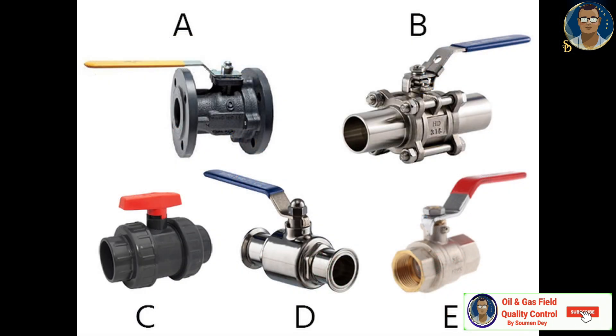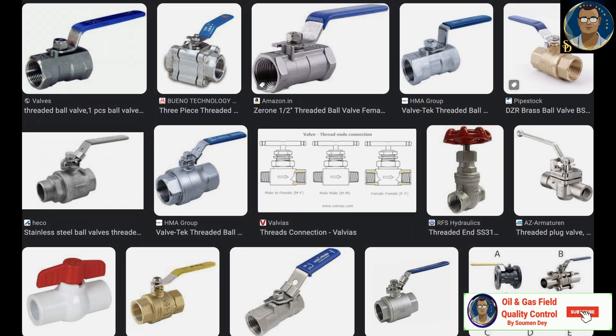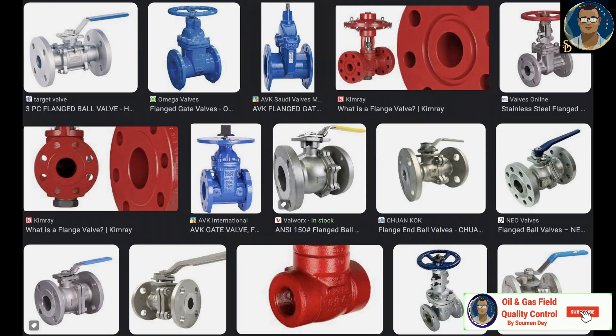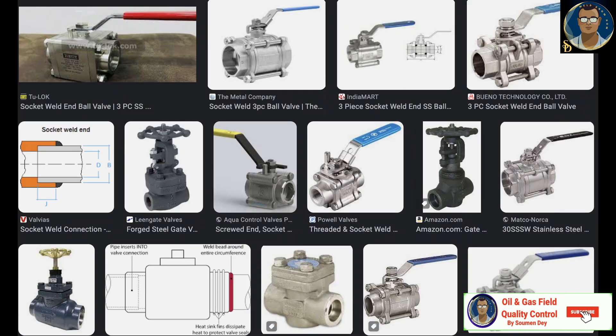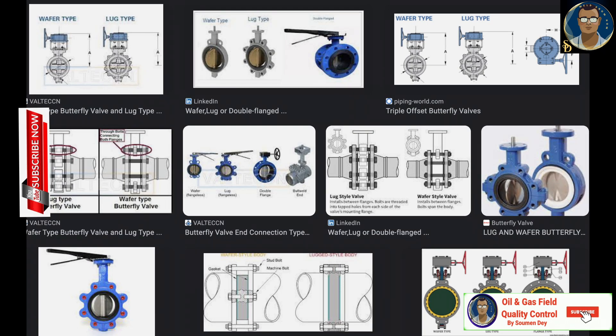Types of valve based on their end connection. The connection type must be compatible with the piping. Types include: screwed or threaded, mostly used for instrument or sample point connections; flanged, one of the most commonly used ends for piping; butt welded, widely used in high pressure and high temperature operations; socket welded, used in small bore piping where threaded connections are not permitted; and wafer and lug, commonly used for compact valves in systems with limited space.